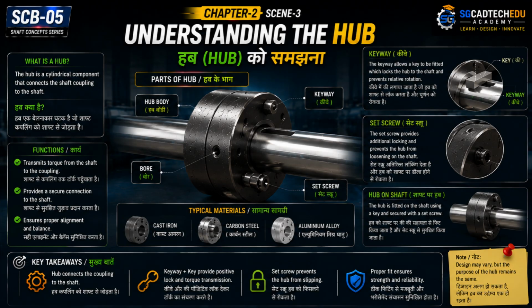The hub contains a precision-machined bore that matches the shaft diameter, ensuring a proper fit. To prevent slipping under load, a key and keyway are generally used to lock the hub and the shaft together, allowing torque to be transmitted safely.